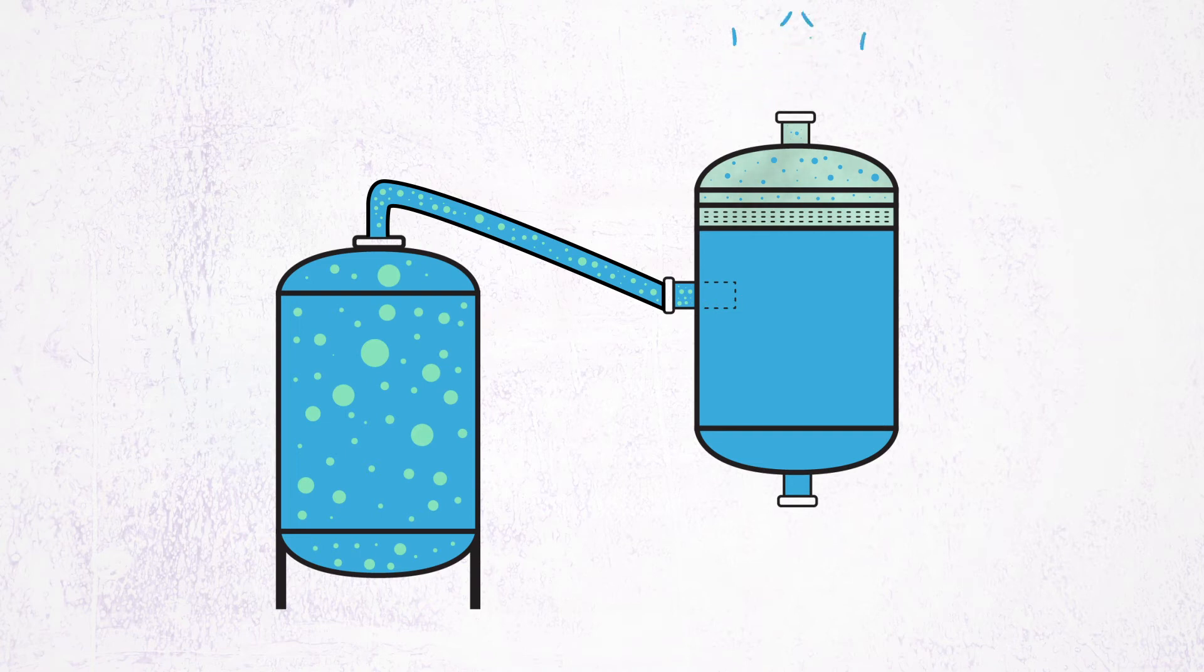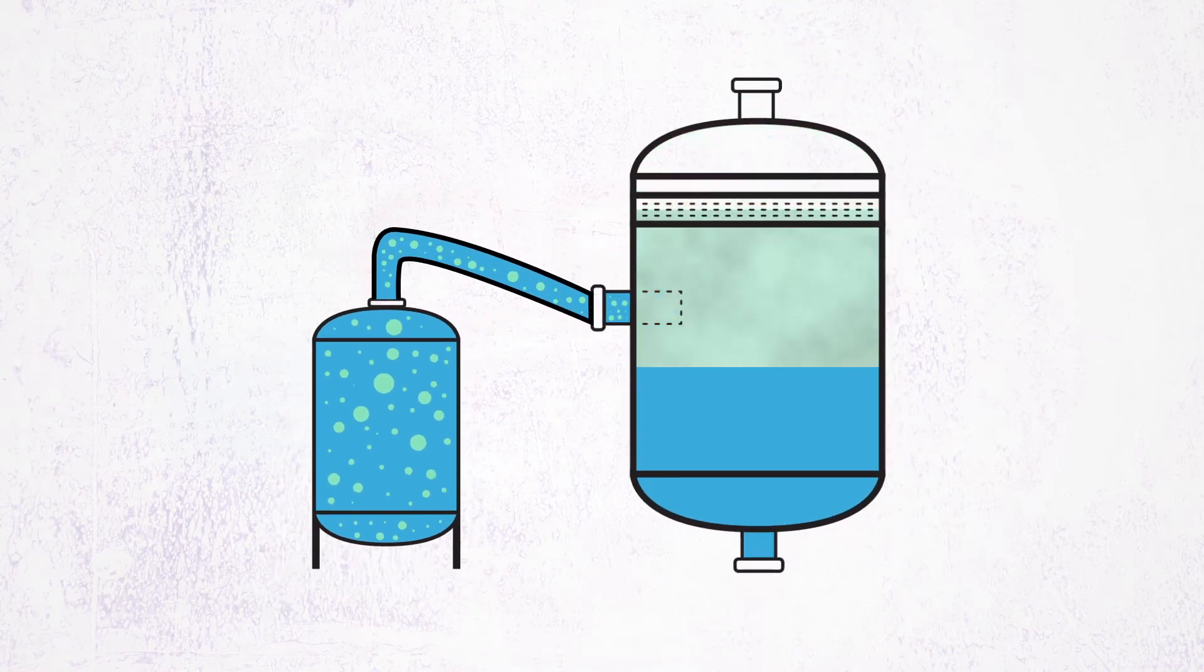As a rule of thumb for reactive upset scenarios, knockout tanks typically need to be two to four times the volume of the process vessel that could discharge into it.